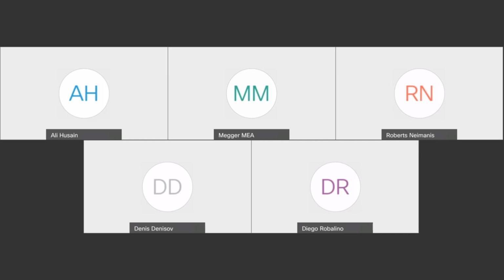What I would say is that not only the nameplate, but the installation file, the commissioning file is the one that I would look at the most for the C2. But the main assessment will be on your C1. There are some specific bushings. For example, you need to understand 2 things. You may have a test tap and you may have a voltage tap, so the construction of those 2 is also different. I think that we can have a session just on bushing assessment. It's a very interesting topic, and what I would like to do, Mr. Jana, is to probably send you a couple of papers that we have published about bushing assessment and validate with some additional information from different manufacturers, especially related to C1 and C2 analysis.